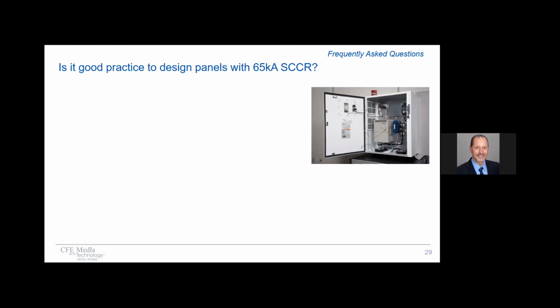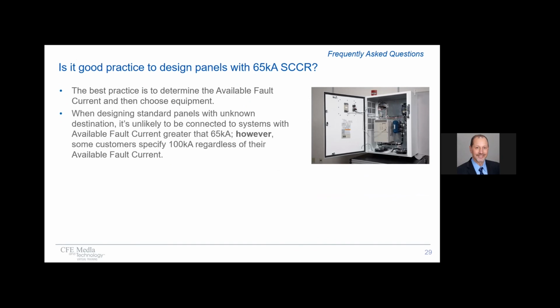Next question. Is it good practice to design panels with a 65,000 amp withstand rating? Well, the best practice is to determine the available fault current and then choose equipment. But when designing standard panels with unknown destination, it's unlikely to be connected to systems with available fault current greater than 65,000 amps. However, remember, some customers specify 100,000 amps regardless of their available fault current.